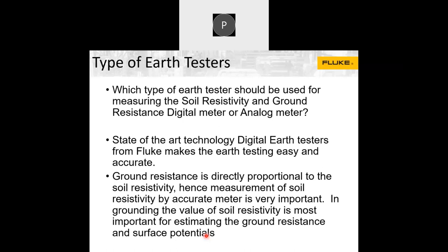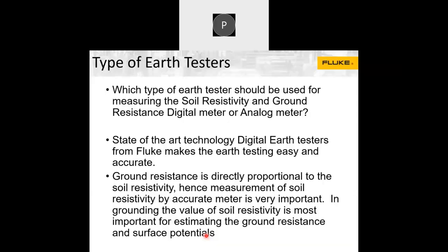Similarly, what kind of earth testers do you need, and what kind should you use for measuring soil resistivity? Earthing is actually designed based on the soil resistivity, the resistance of the soil present at that facility. You have to find the resistivity first, and then decide what kind of earthing you need to do, whether pipe earthing, mesh earthing, or plate earthing.